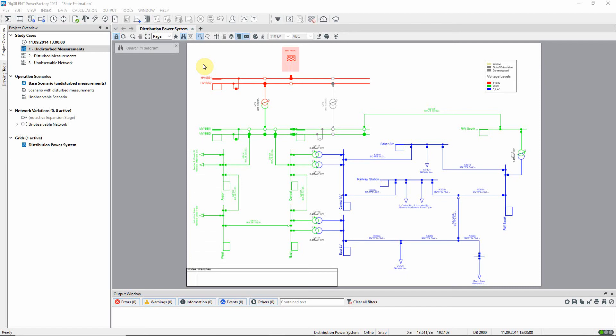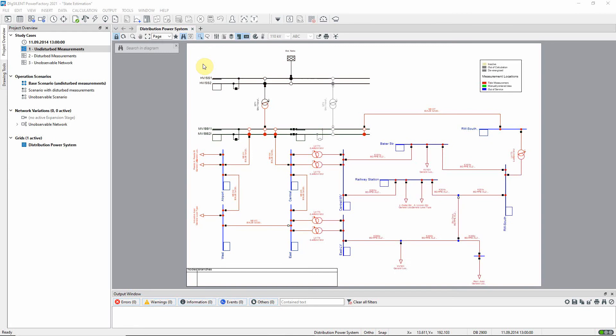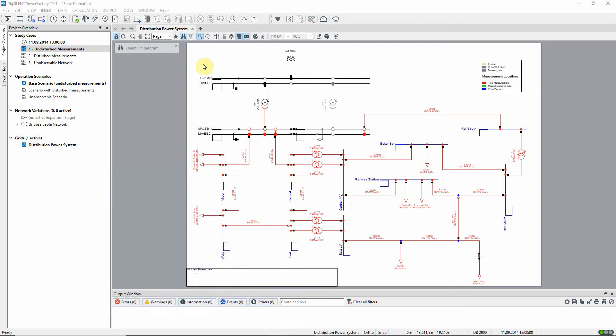The state estimation function is used to obtain consistent load flow results based on measurements which have been imported into Power Factory. For example, branch flows and bus bar voltages. The states to be estimated might include the active and reactive power of loads and generators and the tap positions of transformers.